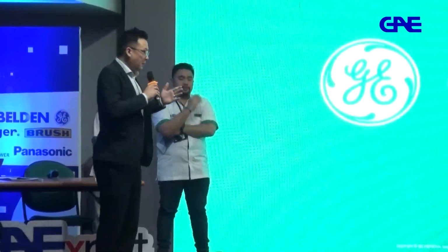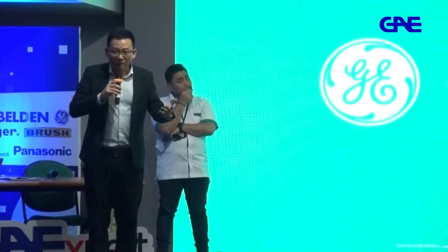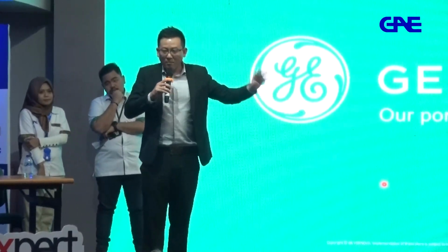Of course, if you still remember what I said, for one gas, hydrogen, when you identify that fault condition, you must always take into consideration the other gases. When it comes to what you mentioned, not just DGA, I want to monitor my bushing as well. Can you provide a one-stop solution, one-stop software? Yes, the answer is yes. We can identify it to you at a glance. Probably I want to see bushing monitoring, rather than just saying I'll show you a software.